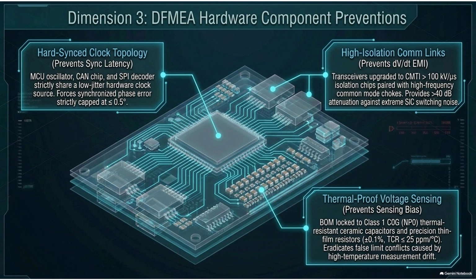Right, because most standard capacitors like X7R types lose a huge percentage of their capacitance as they heat up. They do. But the COG dielectric material is specifically engineered to maintain a flat capacitance curve regardless of thermal stress. So it measures exactly the same at 150 degrees as it does at room temperature. Exactly. But hardware stability is really only half the solution. The other half addresses the motor's magnetic saturation.